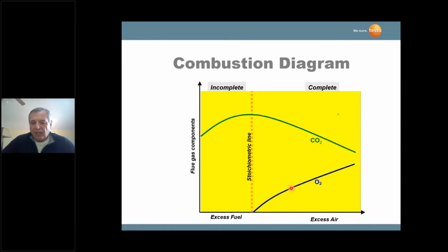Conversely, carbon dioxide, which is an inert gas, and we see CO2 on the complete side and on the incomplete side. But CO2 is a byproduct of combustion. You're going to see CO2, carbon dioxide, in percent CO2. So as we increase our air in the burner, if you're looking at CO2 on your instrument, it's going to go down according to the amount of oxygen that is added to the burner. CO2 is found on both sides of the curve, but you'll notice here that oxygen is not present on the incomplete side, which means that you have too little air and excess fuel.